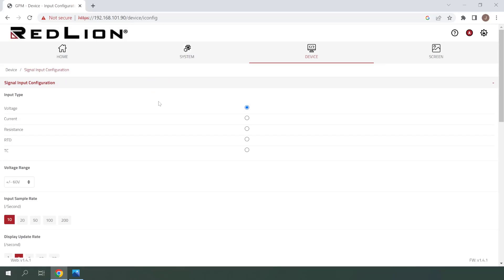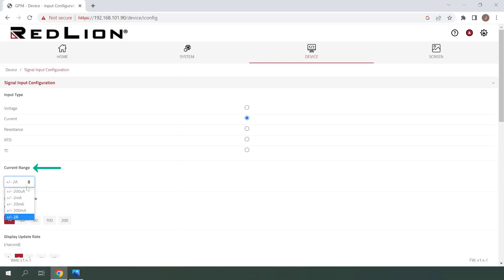The first thing that we see here is input type, and since I'm using a 4 to 20 milliamp signal, I'll be selecting current here. For current range, I'll be selecting plus minus 20 milliamps to account for the full range of my analog signal.